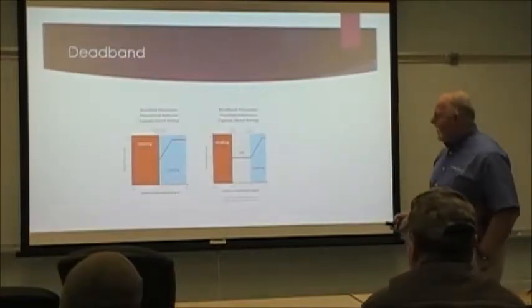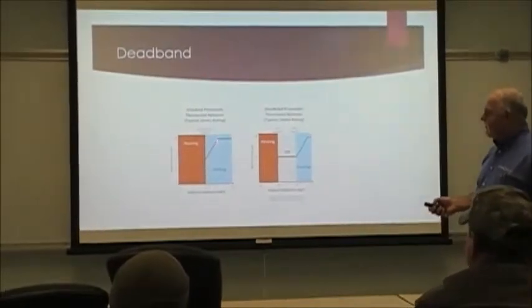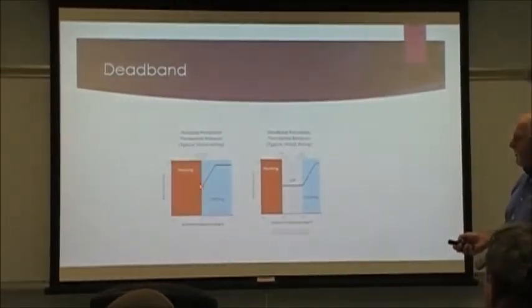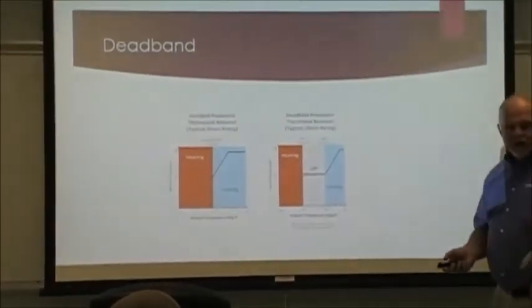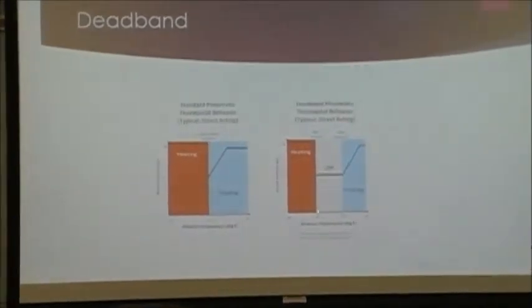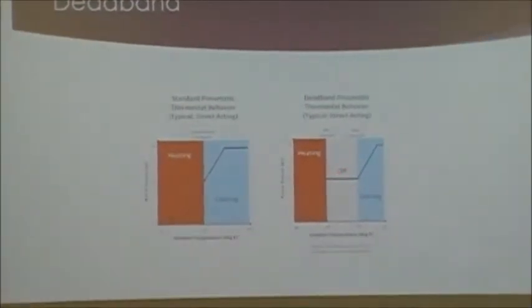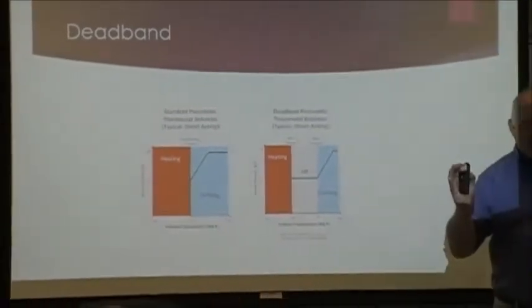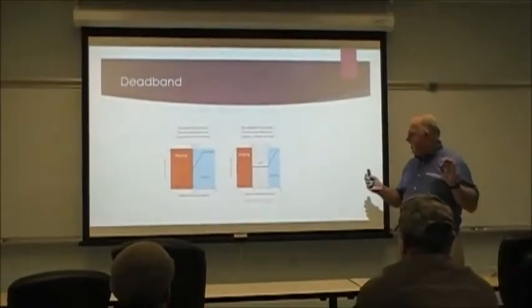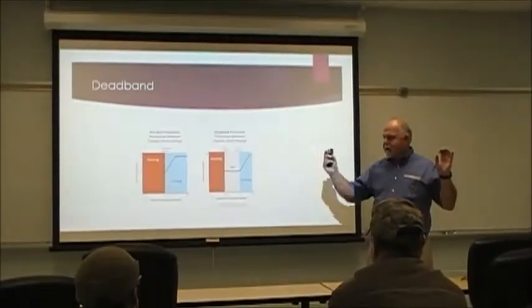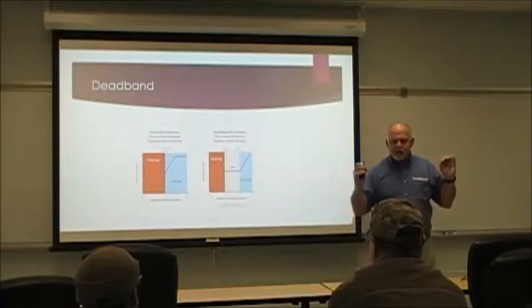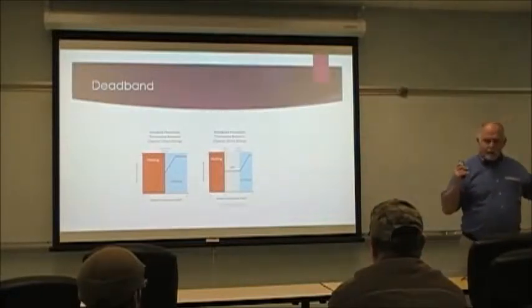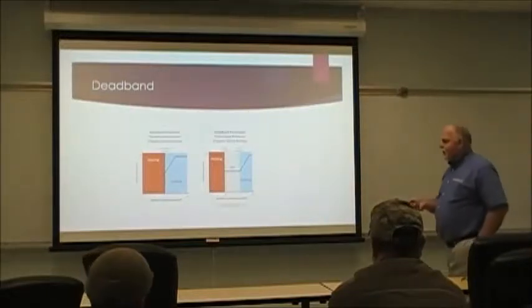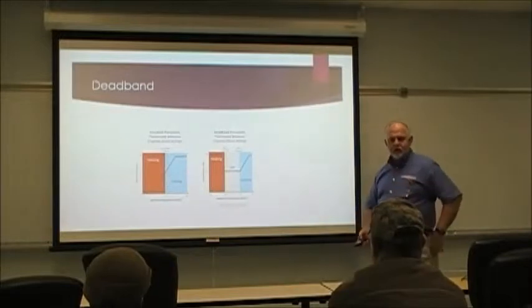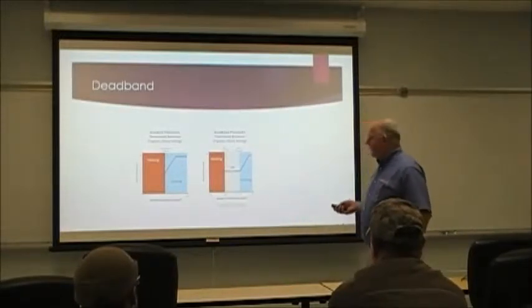The deadband is a period of time when you go from heating to cooling. You see, if you follow it transitionally right there, it goes up. There's a point where it can kind of be like toggling back and forth between heating and cooling. You don't want that to happen. That wastes energy. So they create a deadband, and that is a period or temperature where nothing happens. There's zero heating or zero cooling. Okay, so imagine you have a cooling valve and a heating valve, and as the temperature comes up, your heating valve begins to close off, it goes to zero, it goes through this deadband period, then your cooling valve begins to open. The deadband typically keeps that from toggling back and forth between heating and cooling, okay? And that's an energy saving function right there.